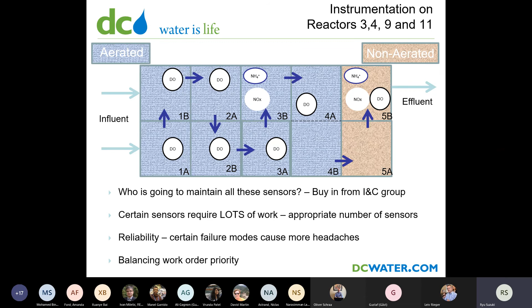And just because of the shortness of time, I also want to quickly talk about balancing the work order priority, because a lot of our maintenance groups are stretched thin. They just have to take care of the rest of the plant. So this is only a small portion of it. A lot of times their main focus is going to be on permit-sensitive items or something related to throughput. So that's where all their priority is going to be. So say if an ammonia probe is out of calibration, they can't necessarily get to it right away because there are other more pending issues. So sensor maintenance and any kind of I&C maintenance is tough.